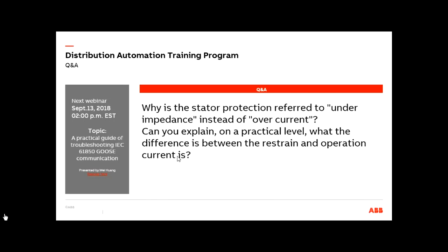In the event of an internal fault within the protected zone, the differential or operation current will be high enough to make the operation win over the restraint. The restraint current will be lower and the operation current will be higher in the event of an internal fault, and the relay will eventually operate. Whereas in the case of an external fault, the restraint current will be higher than the operation or differential current. So that's how the system is stabilized in the event of an external fault. That is the practical side of it, and this is derived inside the relay. We are not feeding different CTs for it. It is derived based on the current from both sides of the generator.